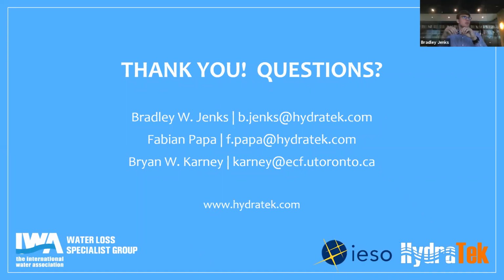Hi, Alan. Fabian here. I'm responding to the part of the question about kilowatt hours per meter cubed, which is typically called specific energy. I agree that can be a misleading indicator. Normalizing it against head, the dynamic head in particular, we've shown to be very valuable. We've tested a number of pumps and done the normalization, and the curves are very crisp and within a narrow range when you normalize against both flow and head. Remember, a pump is delivering water power, which is the combination of both flow and pressure. Not normalizing against them both, you will end up with a lot of noise in the data.